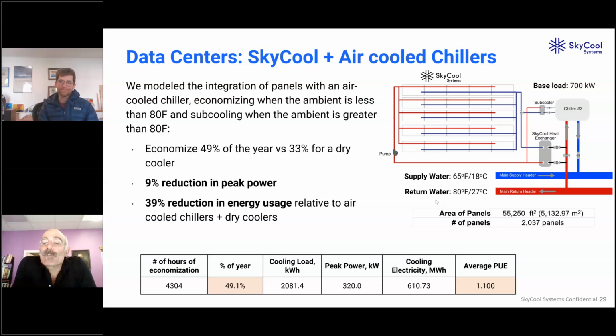Yeah. Okay, is there any application of SkyCool for VRF HVAC systems? We have not done a VRF system. I think it's more complex, just because the VRF controls are often very complex. Yeah, I buy that. I don't know this, but if, for example, the expansion valve is in the head unit inside the building, and you just have liquid refrigerant going from the condenser outside to inside, you may be able to have a heat exchanger there to cool that refrigerant liquid. But I don't know the details of VRF systems and how they're constructed, but it would depend on where essentially the expansion valve is. Yeah, I think better to start here and then expand out. For sure. For now, VRF's out.